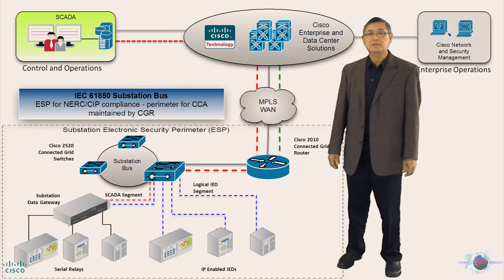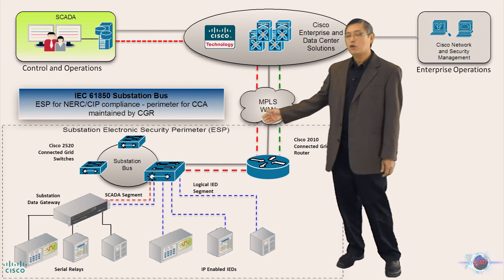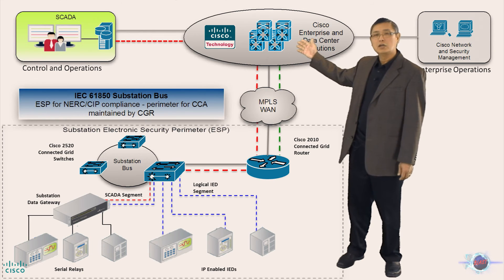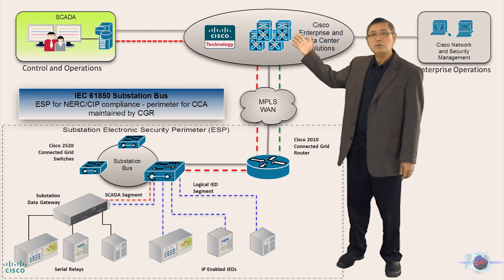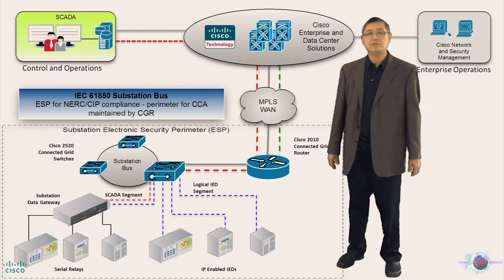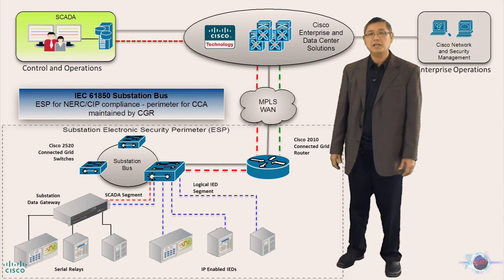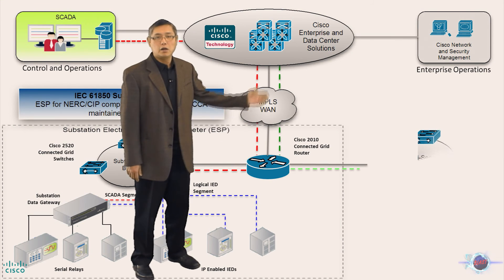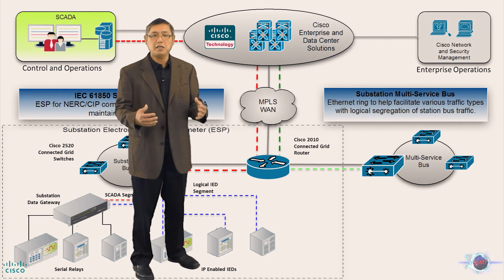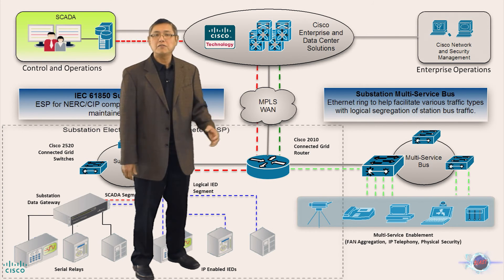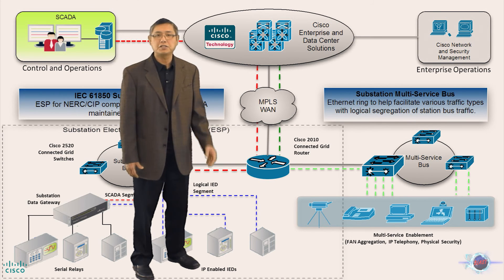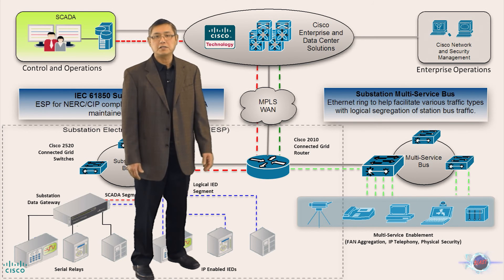We also observe the different traffic flows in the SCADA polling traffic, which flows from the IEDs through the substation bus, over the wide area network, to the control and operations centers. With the CGR 2010, users are able to apply different levels of quality of service, as well as the ability to create logical segmentation within the network in order to comply with substation regulatory requirements. On this side resides the multi-service Ethernet ring, which allows utilities to integrate advanced services such as remote workforce management, as well as to provide services like physical security for NERC CIP compliance using the Cisco physical access control solution.